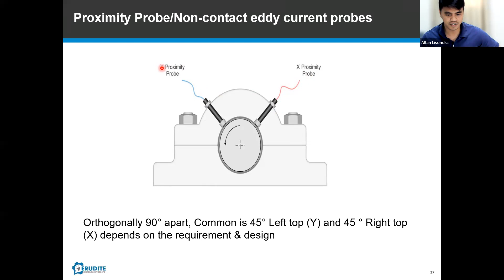Here, the probe cannot be mounted easily at the desired 90 degrees. So out of phase, horizontal and vertical orientation probes often have a 45 degree deviation. This is an example of the convention, like here you have X and Y.